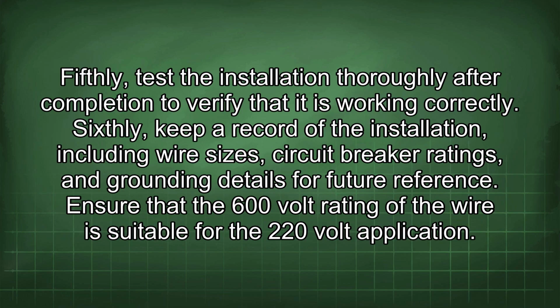Fifthly, test the installation thoroughly after completion to verify that it is working correctly. Sixthly, keep a record of the installation, including wire sizes, circuit breaker ratings, and grounding details for future reference. Ensure that the 600-volt rating of the wire is suitable for the 220-volt application.